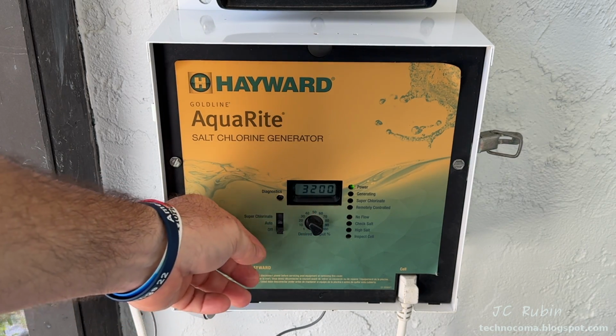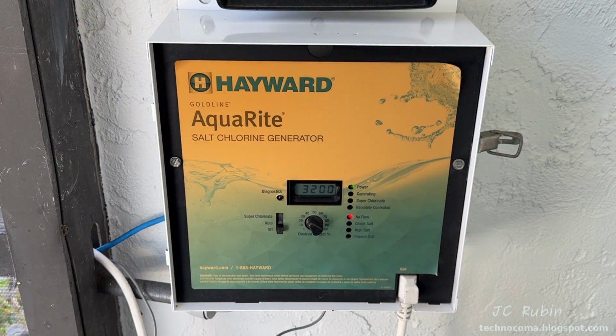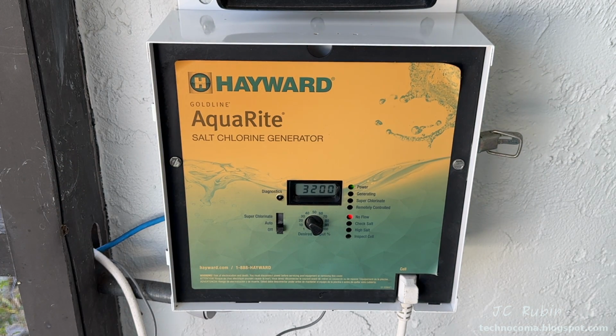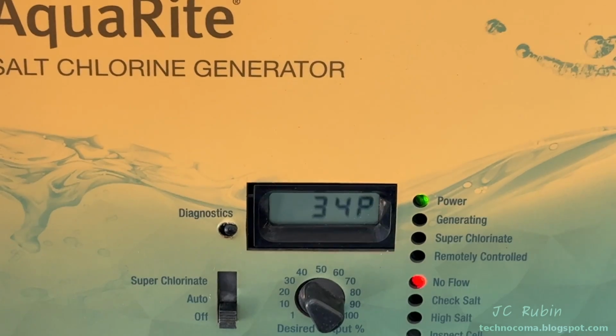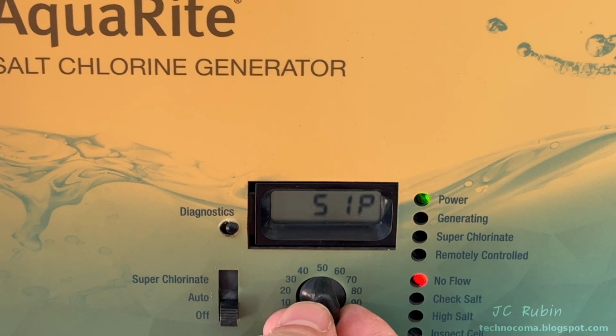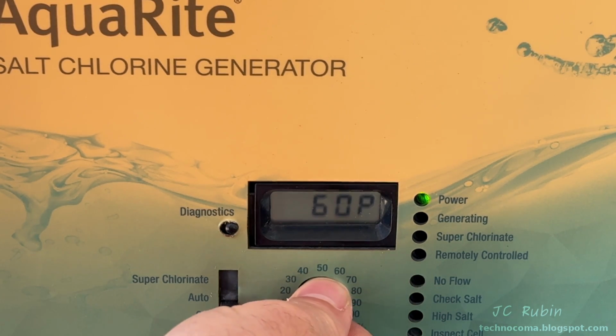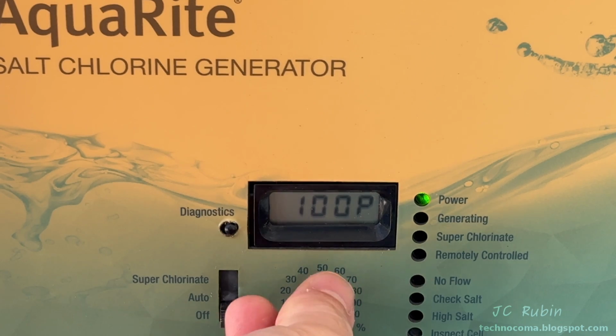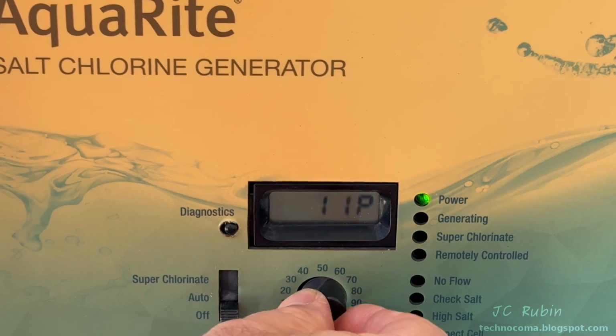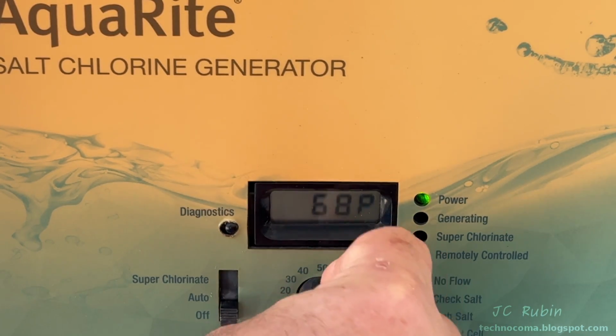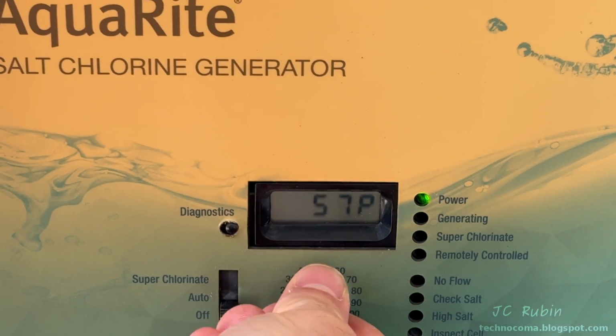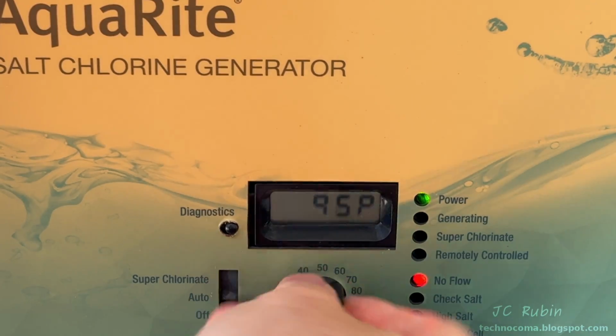We could test the potentiometer before I do. What I want to do is check to make sure I know exactly what setting it's on. I pressed the diagnostic button till I got the percentage, which is 34. We can see the P showing percent, and now I can move it back and forth. The device is in the off position, so it doesn't matter what I set it to - it's not having any effect on the generation.